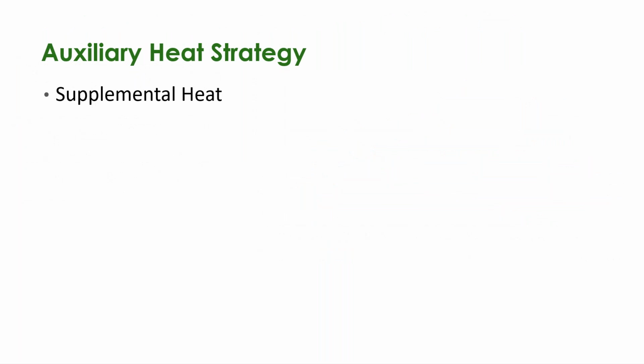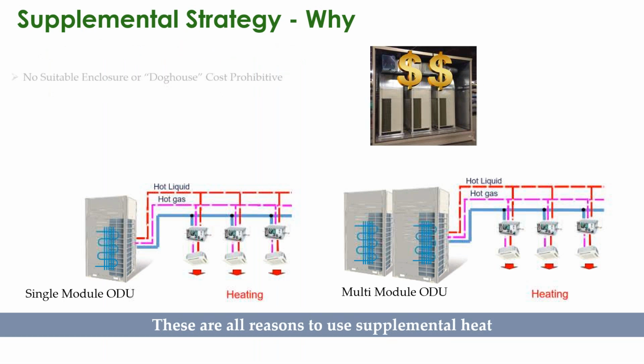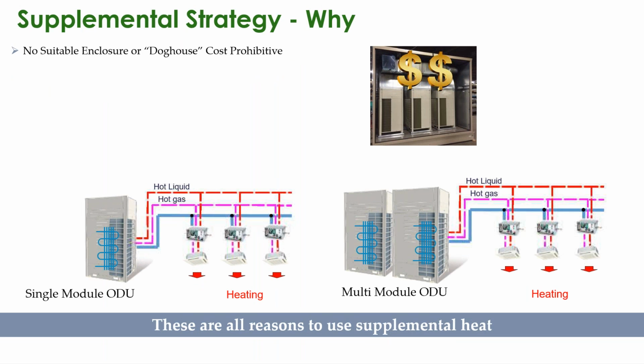First, we're going to talk about supplemental heat as an auxiliary heat strategy. This is very common in areas where we don't get extreme cold. Namely, like my area, I'm in Spokane. We do supplemental strategy a lot because if we get cold, it's going to be cold. We're going to need some backup. But if something fails, it's not critical. Supplemental can get us by until we get somebody out to repair the equipment, and it's not life-threatening. This is a strategy to look at when there is no possibility of using a doghouse or that is cost prohibitive.